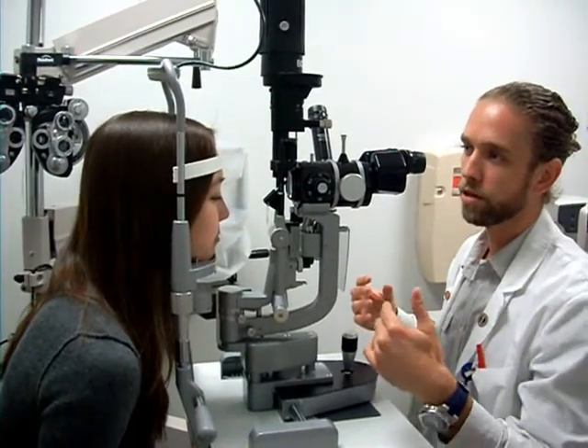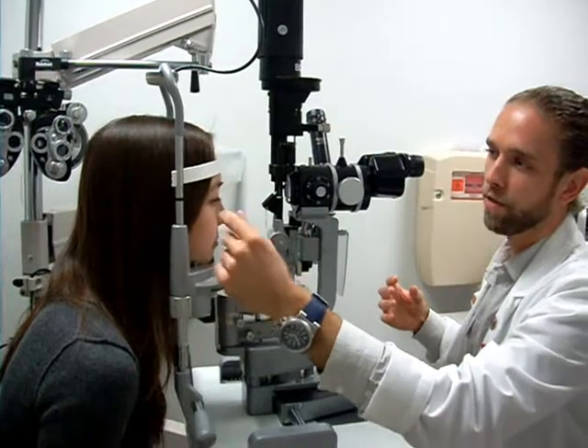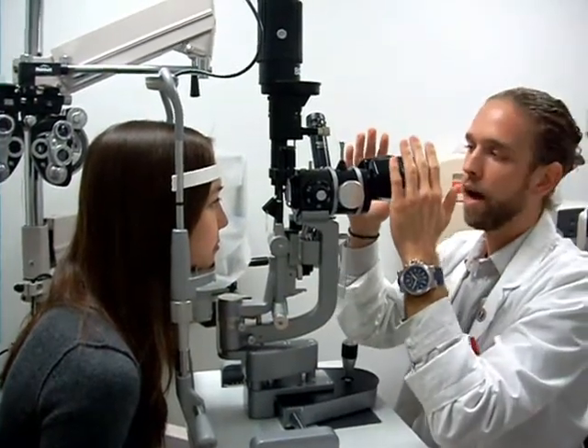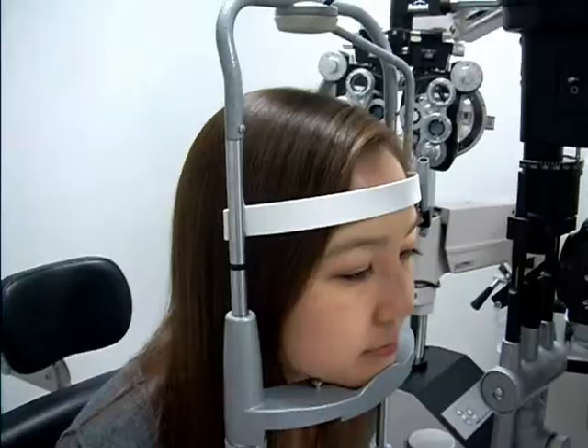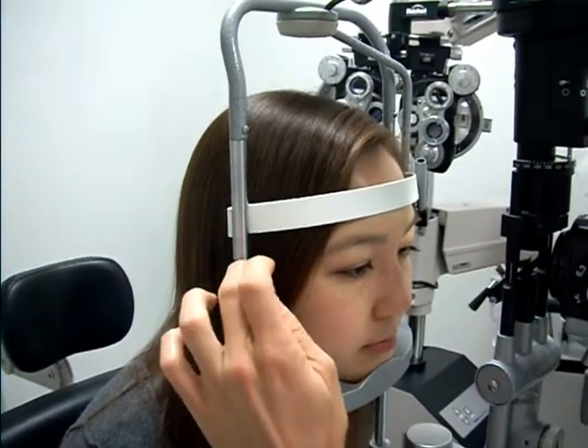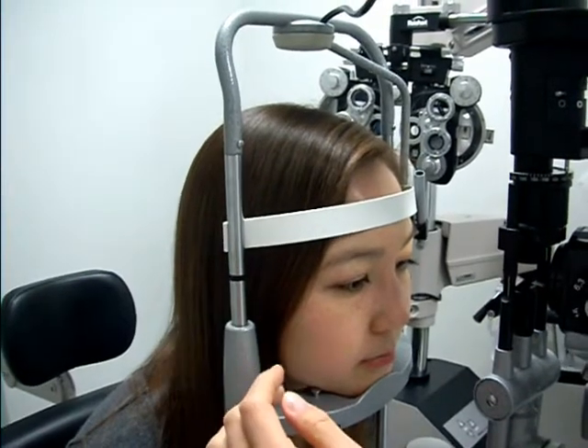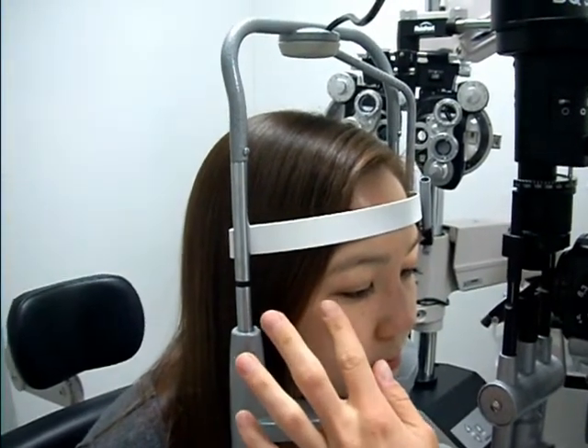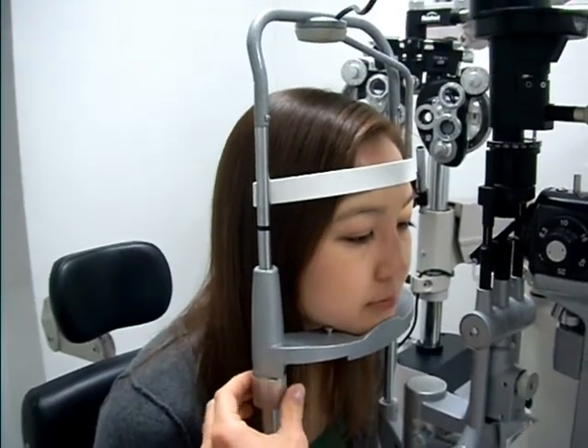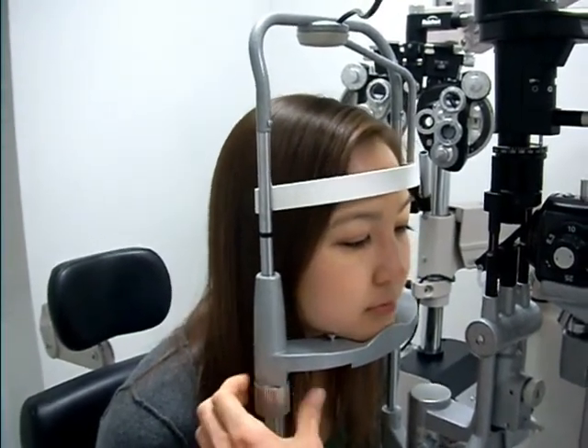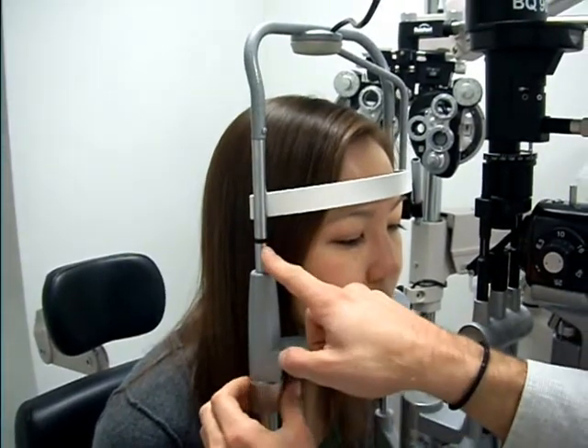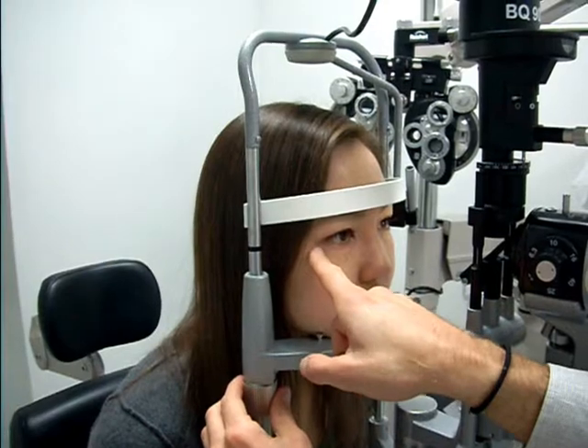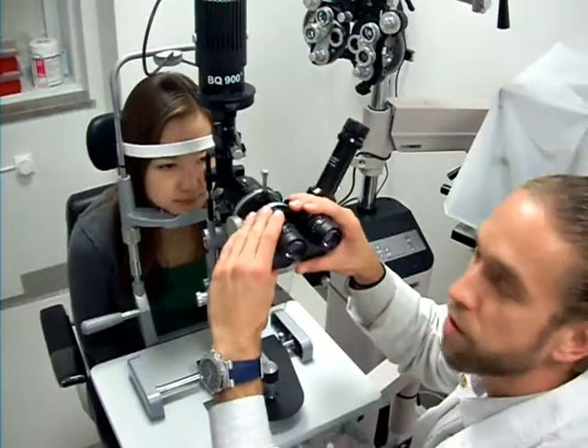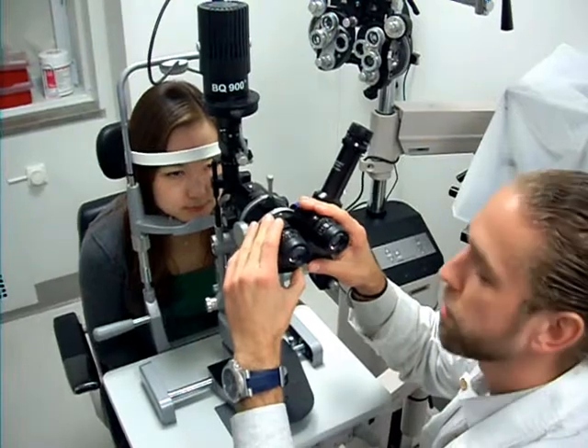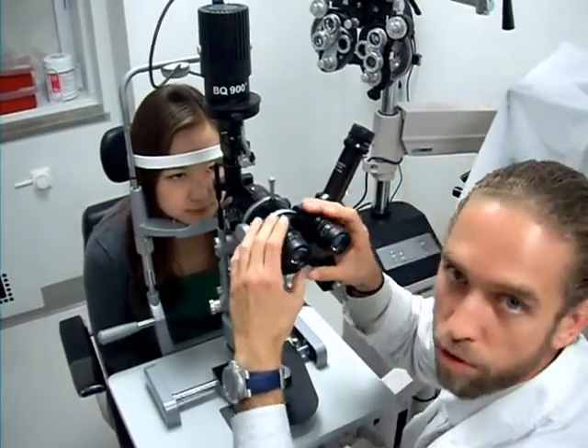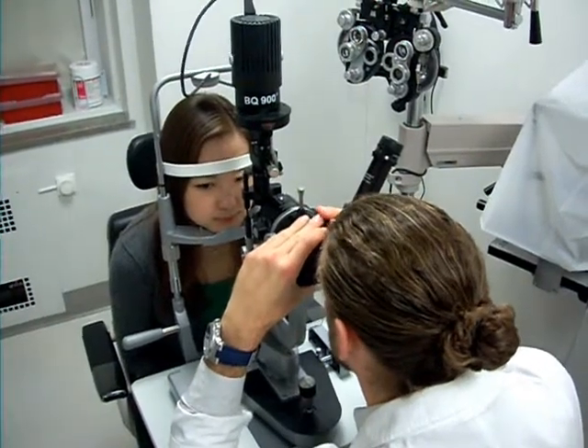One thing that I want to talk about next is the proper elevation of the patient's head and how to set the binoculars on the actual machine. So as you can see, there's a line here on the machine, and that indicates the elevation of where the eye should be. So there's a knob right here that can lower and elevate the patient's head. So you want to make sure that this line is approximated with the patient's lateral canthus. Here you have the binoculars that you're going to be looking through to evaluate the patient. You want to make sure that you start at the 0 mark for both and adjust them to a comfortable level to get a clear picture through the scope.